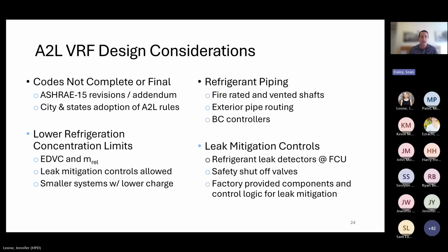And lastly, with the A2L systems, I mentioned it a couple of times, we are going to be providing leak mitigation controls. All of our FCUs on the commercial side will have a refrigerant leak detector built in. On the residential side, most of them will, and if they don't, I believe they will have the option for a field-installed one. So that's all going to come from the factory.